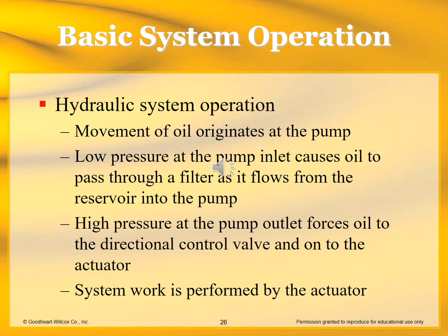Inside the pump, it's basically a low pressure system that lets the atmosphere push the oil into the pump, and then it squeezes it out. That's what creates flow. And that flow and the corresponding pressure gets directed by the directional control valve to where you want it. Then that flow and pressure results in work by the actuator, the cylinder or the motor.